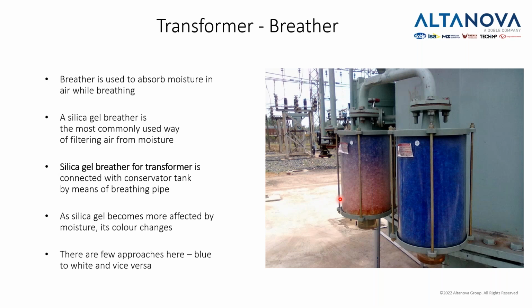The transformer breathes: during the night, when it's not working or is working less, the volume of the oil is smaller. During the day, when the transformer is functioning more, it is hotter, and then the oil expands. So it's bigger, smaller, bigger, smaller, day by day. It basically breathes like lungs.